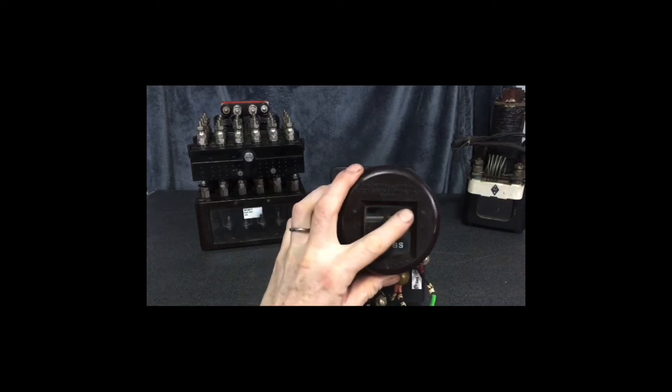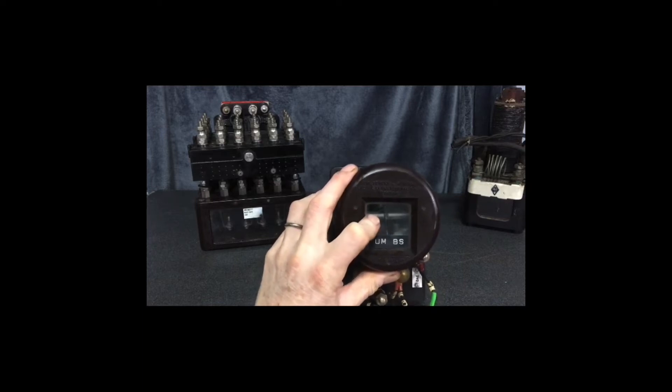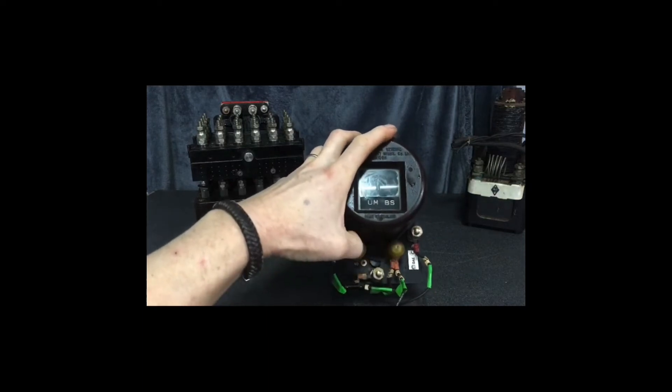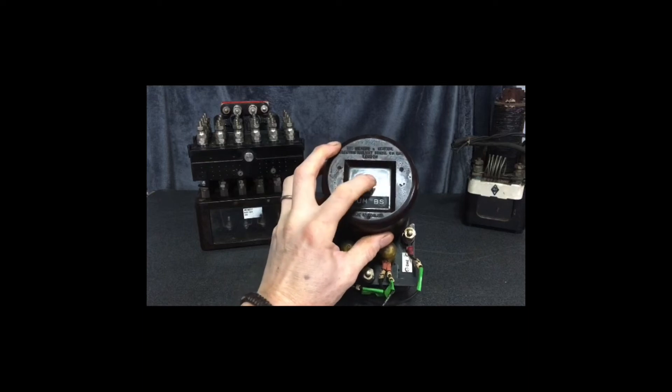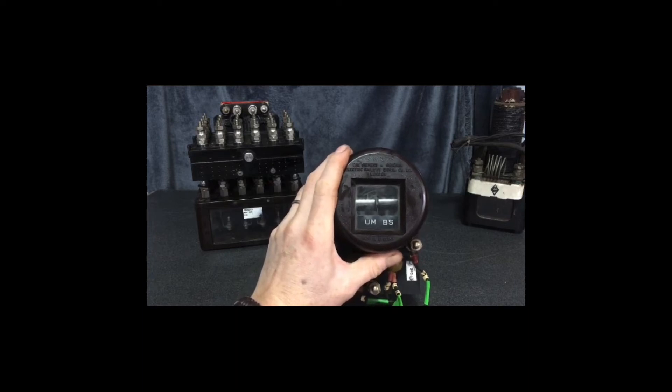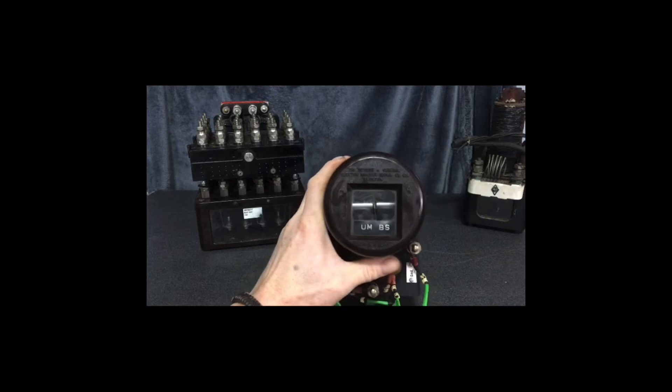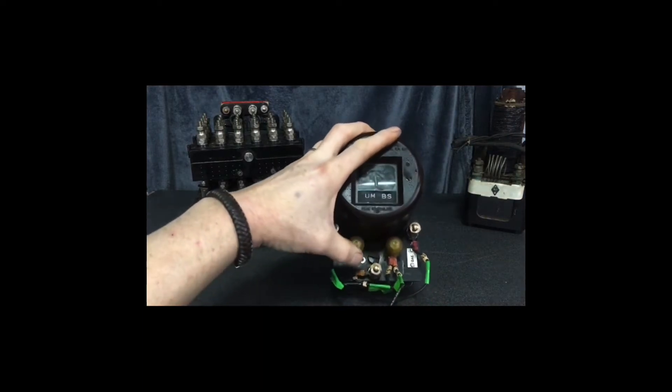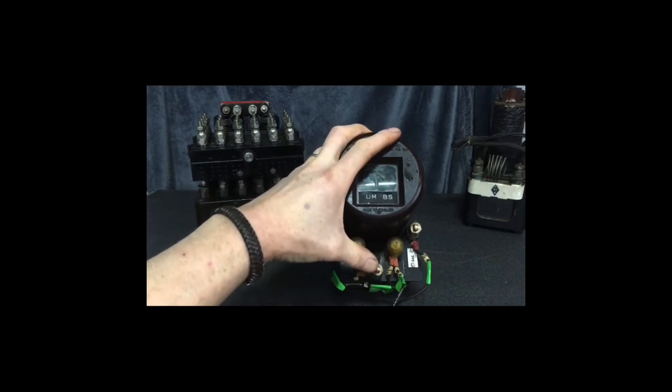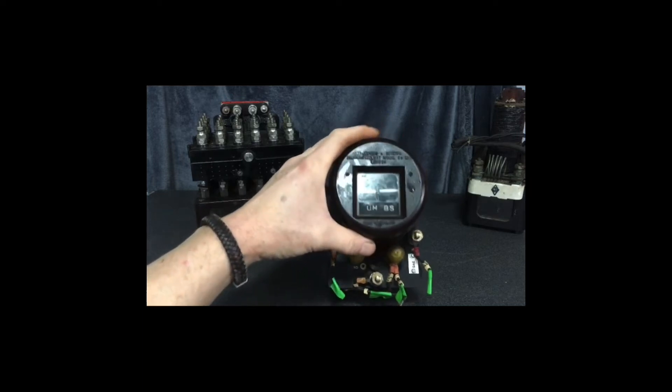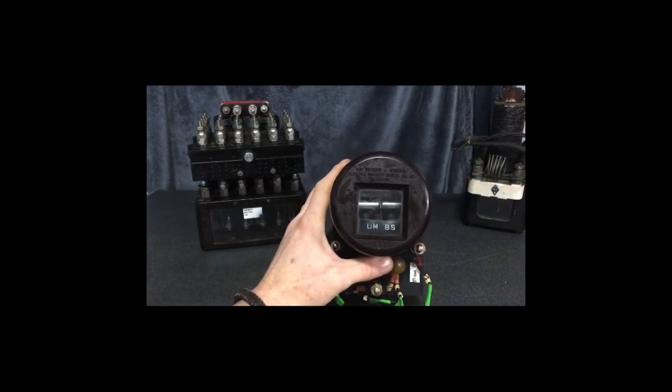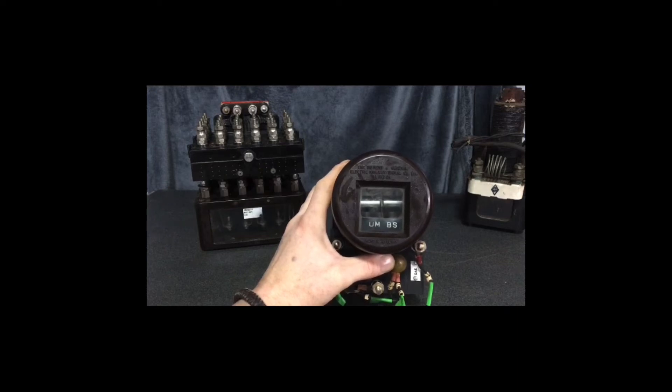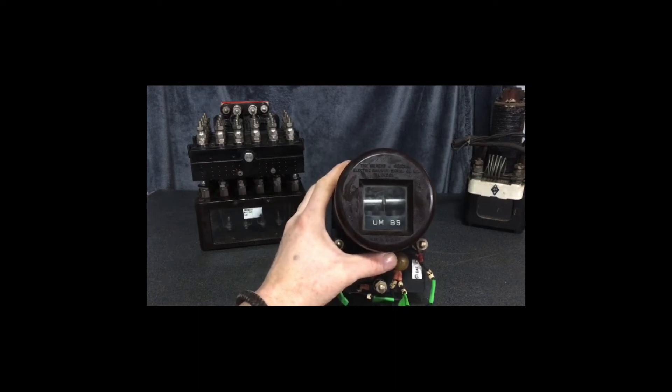Notice it's got like a spring inside that turns it. The second way is you apply the wrong polarity to this. If you put positive and negative the wrong way on the terminals R1 and R2, the contact would simply just bend further into its wrong position, it wouldn't make. The third way is you apply the correct polarity, correct positive and negative to the R1 and R2 terminals, and only then will the contact go over and make the contact that you want. On this one, you'll notice it's got an R1 and R2 for the coils, and it's got an armature and a normal and a reverse contact on that. These tend to be used in block circuits where polarity drives the blocks one way or the other, gives you a line clear indication or a train on line indication. It's quite important that you only have the relay picking with the correct line clear indication.